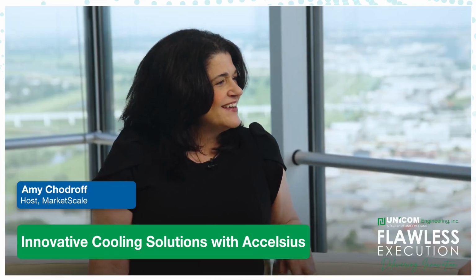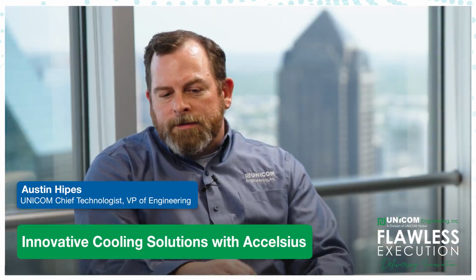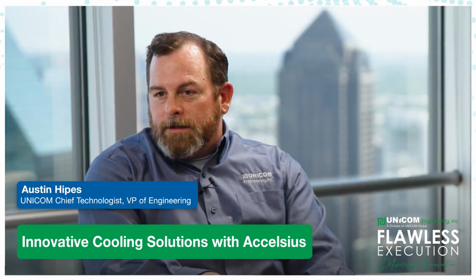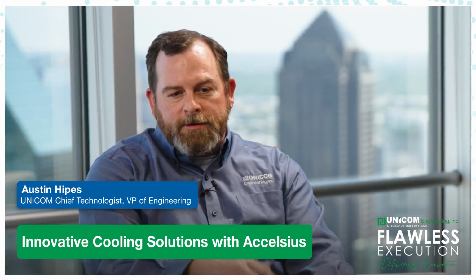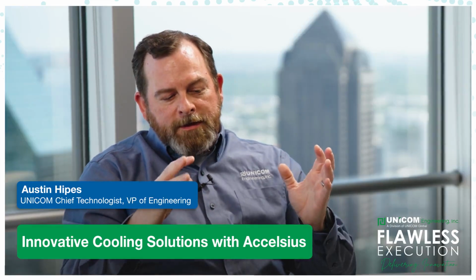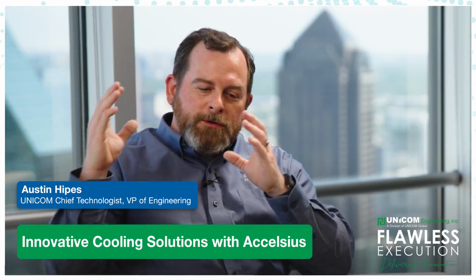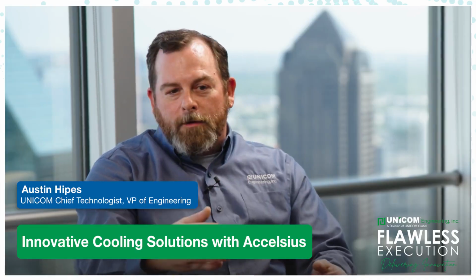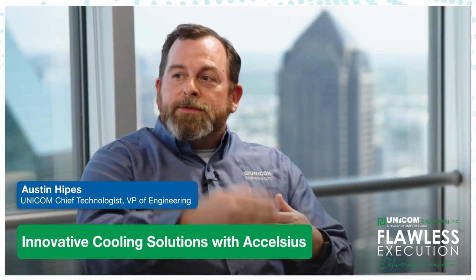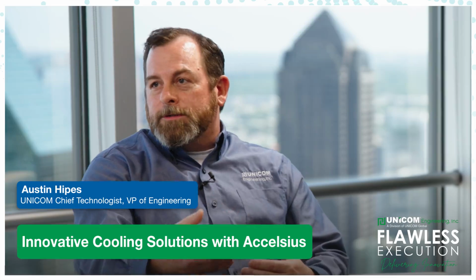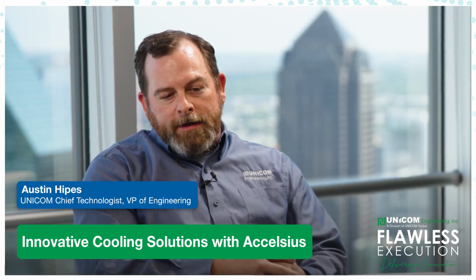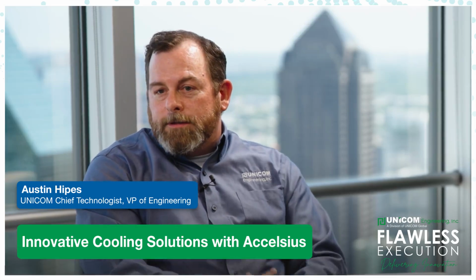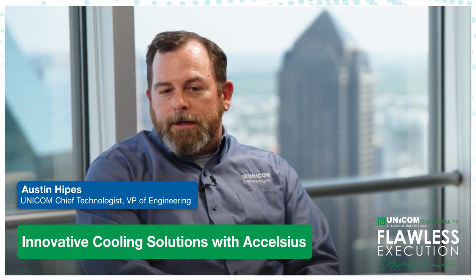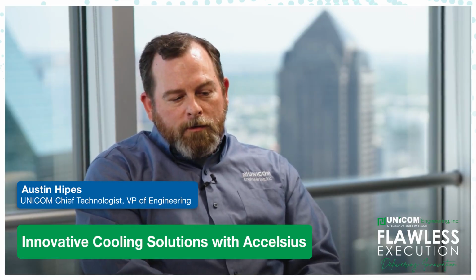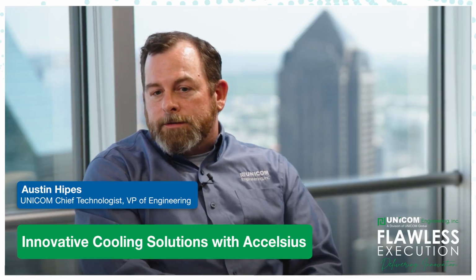Austin, would you like to weigh in on the conversation? Yeah, so essentially some of the advantages in two-phase liquid cooling, especially cold plate, is that it's allowing you to essentially take your air conditioner straight to the chip. You're not having to go through air, you're not having to go through water, and the more loops you can get out of the process, the more efficient your cooling is going to be. It also allows for much higher heat rejection than some of the other solutions available today, whether it be air-cooled or a more single-phase cold plate solution.